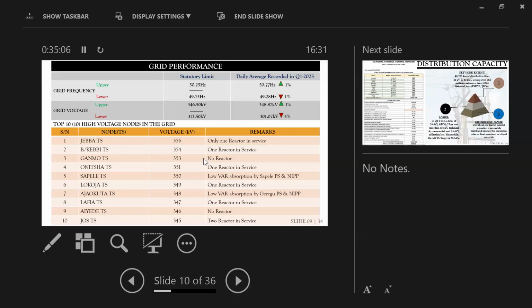Our daily average recorded in first quarter was 348.87, and the minimum is 301.4. I was able to bring the top 10 high voltage nodes in the country, just picking a reading of one day. You can see Jebba has 356, B/Kebbi has 354. And where there is 356, we only have one reactor in service; at that particular moment, we have two reactors and one is out. We have Ganmo 353, it has no reactor. Onitsha 351, one reactor in service. Sapele TS, you have 350. And Lokoja, you have 349, one reactor in service. Ajaokuta 348. Lafia TS has 347. Ayede TS has 346. Then Jos TS has 345.